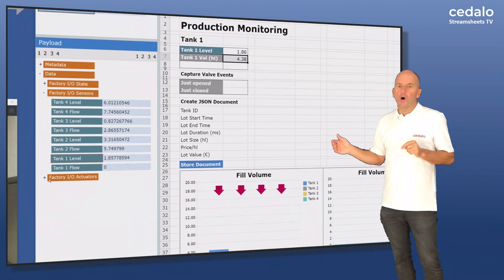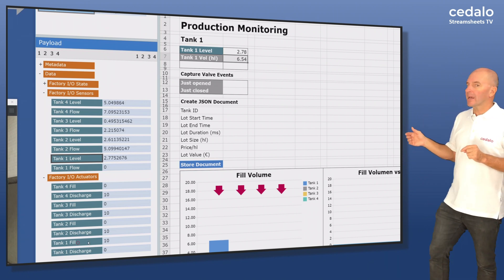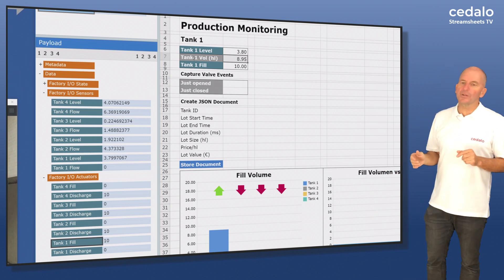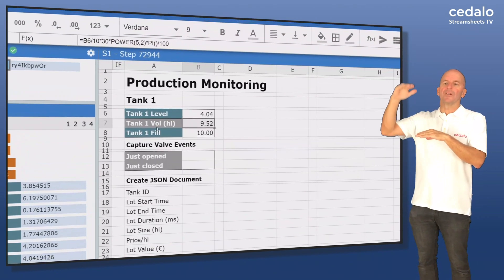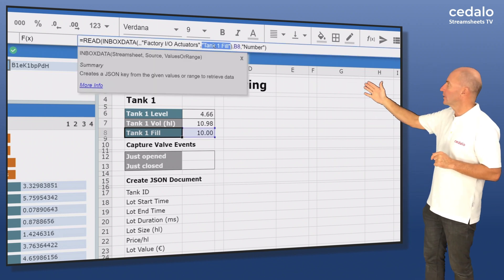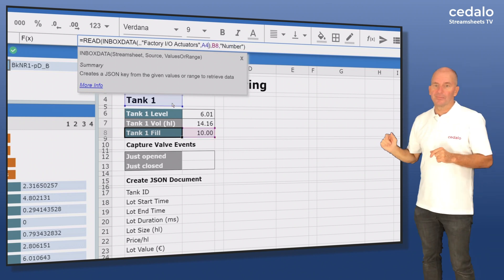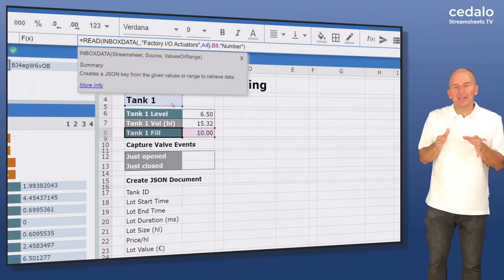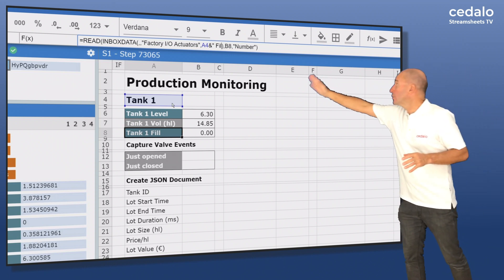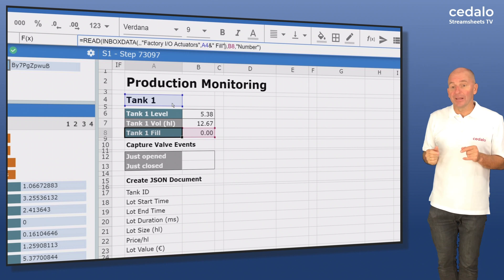Then we need the open-closed status of the fill valve. To do this we drag the corresponding JSON field onto the sheet. A closed valve has the value zero, an open valve has the value ten. We would later like to reuse the read formula when we copy the formulas for the other three tanks to the right. The trick is that when we do the autofill later, it will create labels for tank 2, tank 3, and tank 4 automatically — that's why we added the formula syntax here.